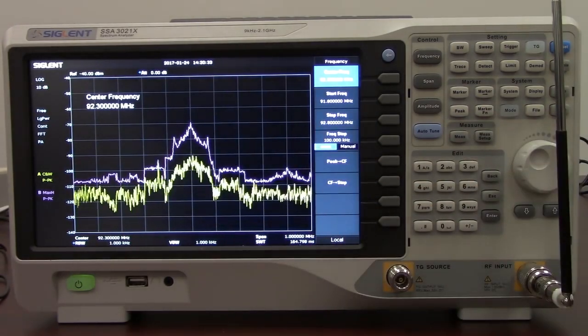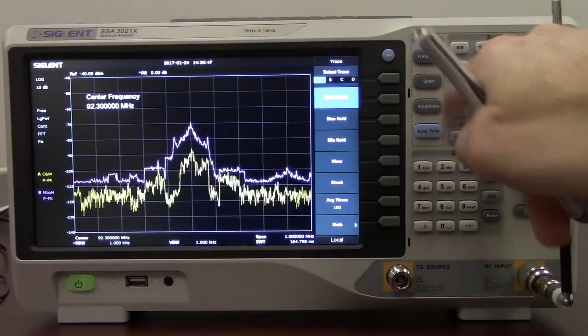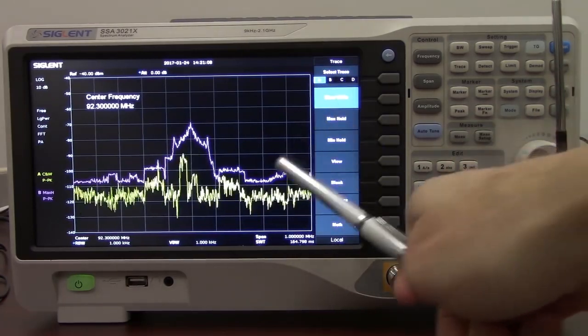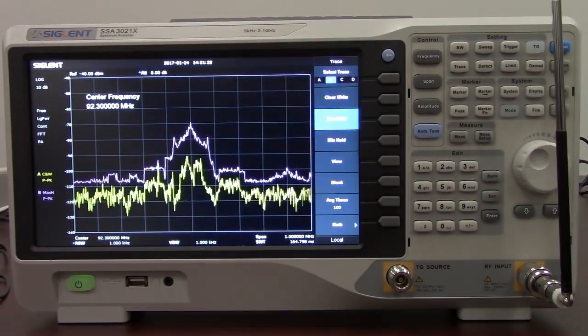Again, this is a useful tool for this particular job because we're visualizing the actual output. Now the purple trace that we have here is a secondary trace. You can access that by pressing trace. Here with this instrument we've got four traces available. You'll see clear write. Clear write is the trace type that we show with the yellow trace, which is trace A here. And that's actually overriding. Every time we've scanned through that particular frequency span we're getting new values for each individual frequency bin. And purple here is going to, which is B, is in max hold. And that max hold is then going to show us the maximum value. So over a span of 10 minutes we actually get the envelope that this particular transmission is also taking up.